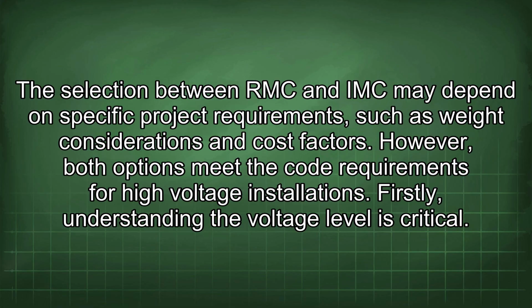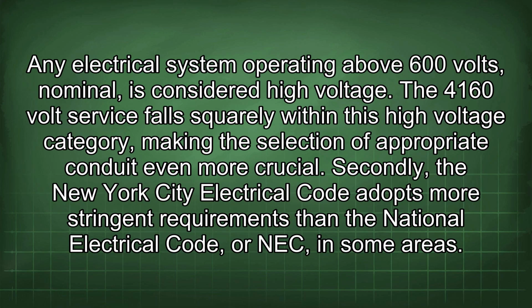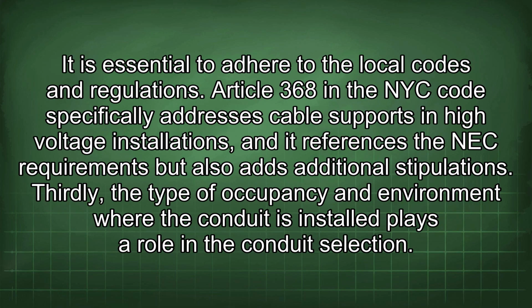Firstly, understanding the voltage level is critical. Any electrical system operating above 600 volts, nominal, is considered high voltage. The 4160 volt service falls squarely within this high voltage category, making the selection of appropriate conduit even more crucial. Secondly, the New York City Electrical Code adopts more stringent requirements than the National Electrical Code, or NEC, in some areas. It is essential to adhere to the local codes and regulations.